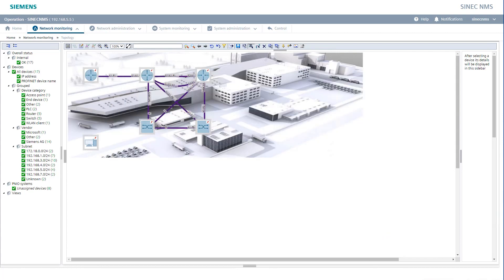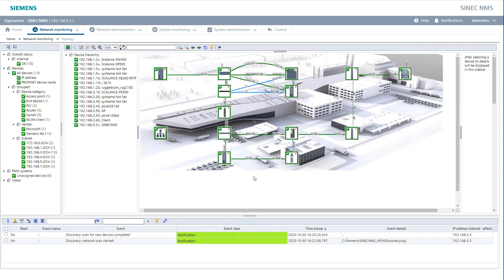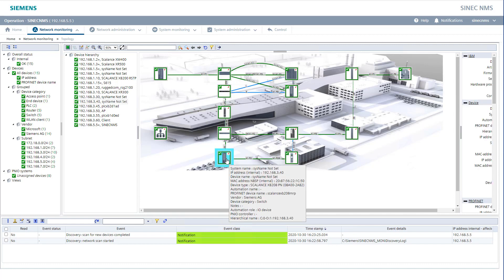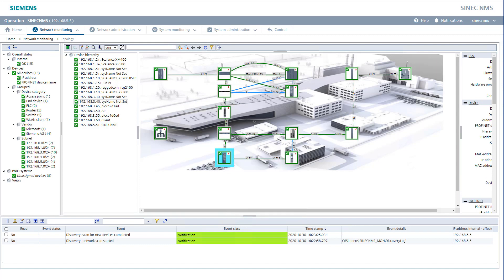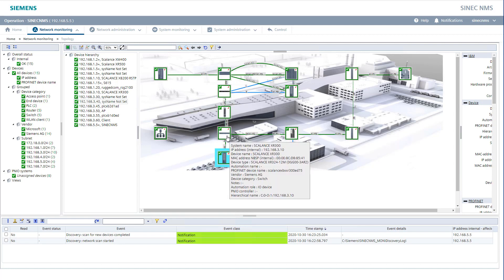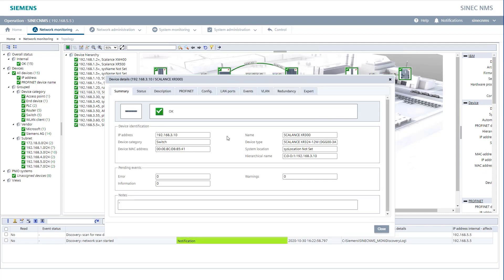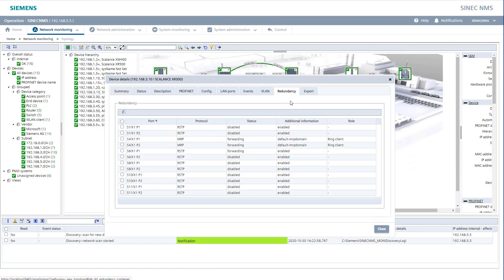This device now depicts the fully read-in topology of our sample plant, which was expanded by three additional scan areas. As soon as we move the mouse pointer over a device, we receive more information about the device itself. In our topology view, we also get information about our connections — do we have optical, electrical, or even wireless connections? A distinction is also made between active and blocked connections, for example when it comes to redundancy mechanisms. By double-clicking on the device, we get all the information that this device can provide to us, for example about the Wi-Fi configurations or the configured redundancy mechanisms.